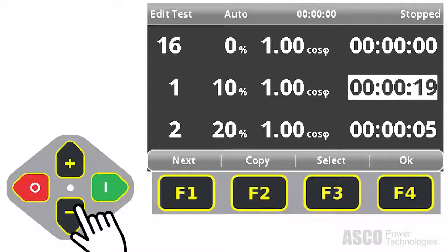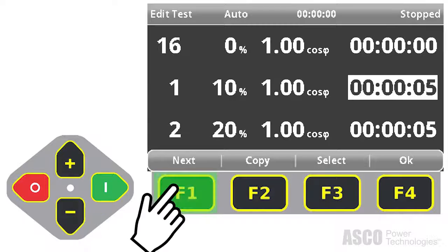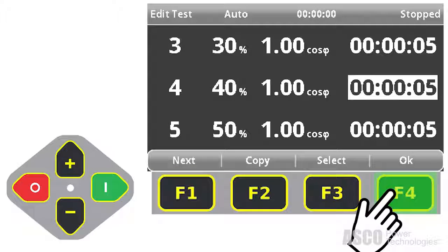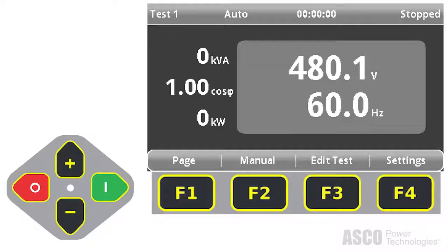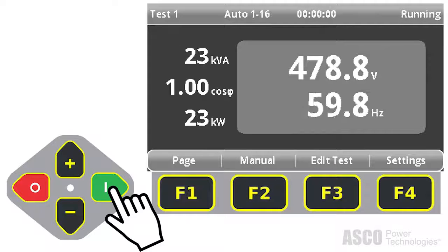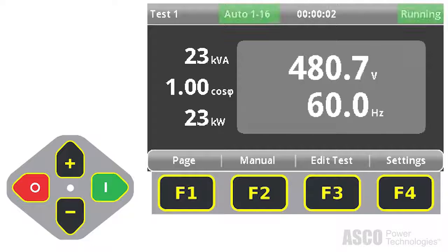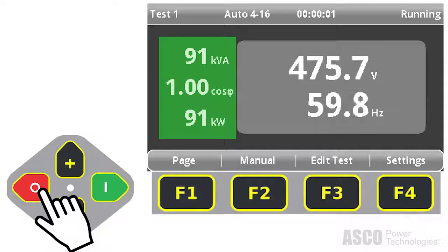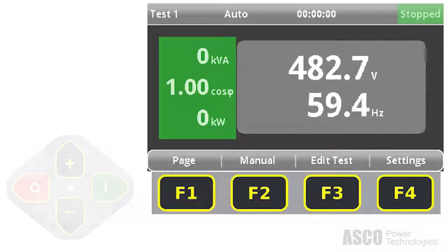So we'll set this one for 5 seconds at 10%. Next we'll do 20% for 5 seconds, then 30%, 40%. So we'll hit OK when we're happy with that. Comes back to this screen and I just hit the accept button to start the test. So up top here we're in load step 1 for 5 seconds. We're at 10% load, and now after 5, we've gone to load step number 2 at 20%. So it'll automatically go through that load script profile for you. If you want to interrupt the test mid-test, you hit the red circle button to reject a load.